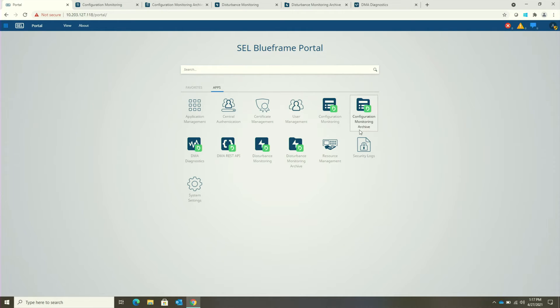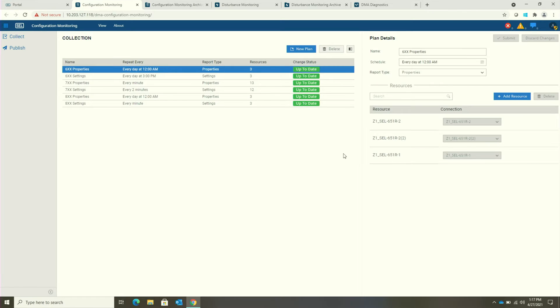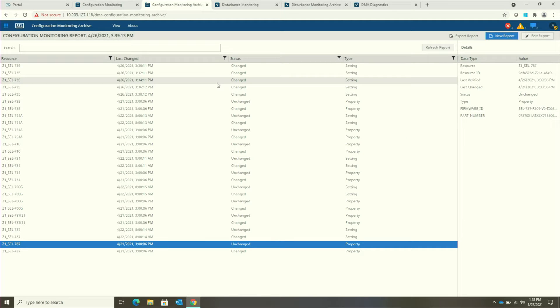Now let's take a look at the actual application packages in BlueFrame. Looking first at the configuration monitoring package, this includes both the configuration monitoring application for defining your plans and the schedule at which you want to collect information from these devices. The information that configuration monitoring collects is both the settings information from supported IEDs as well as the properties information. Once the plan is configured and running against those devices on the schedule you've defined, users can come into the second application in the package, which is the configuration monitoring archive.